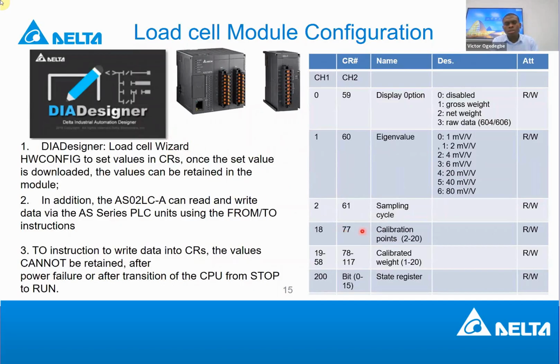Then you can choose this instruction to read or write those very parameters. So this is the calibration point. This is the calibration weight, the weight you calibrate. So it's okay for this point: if I measure this weight, this should be the digital value.